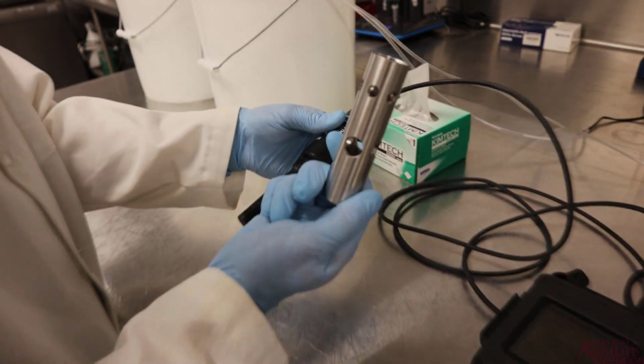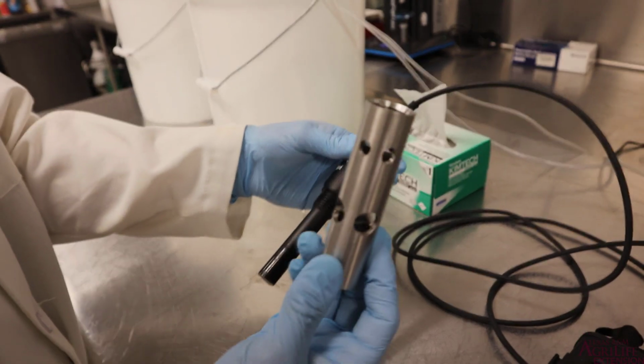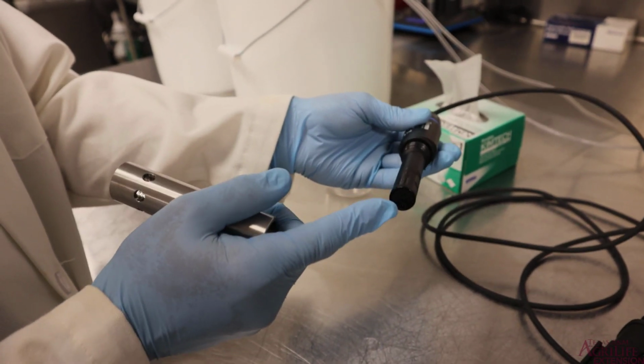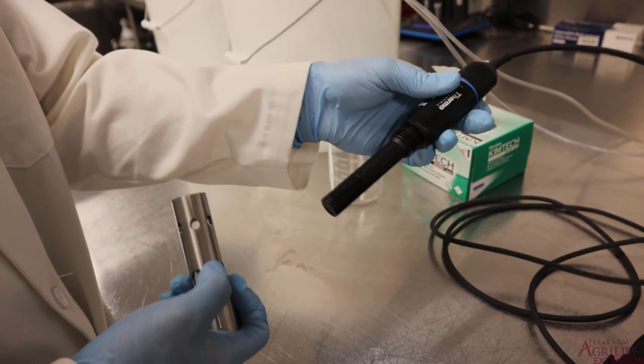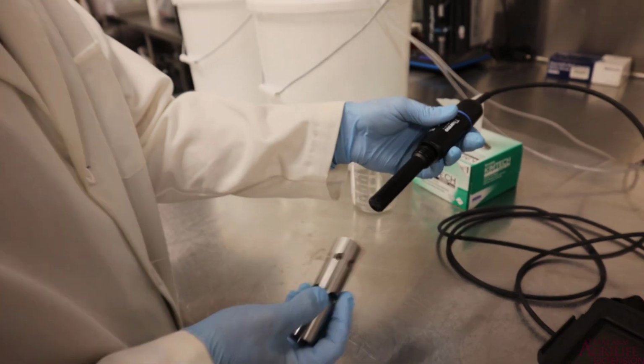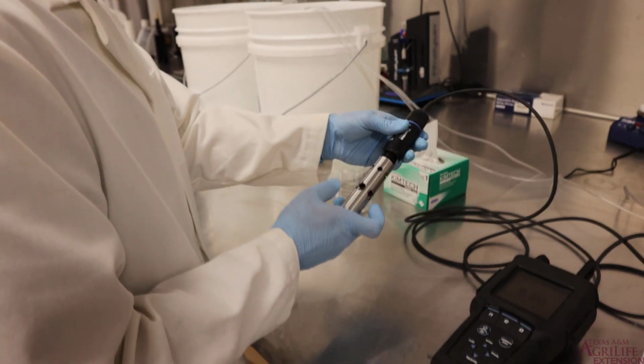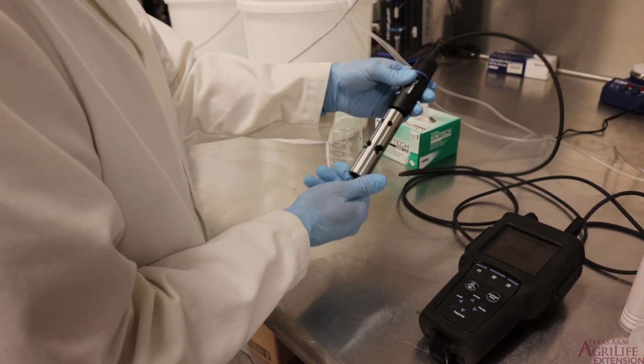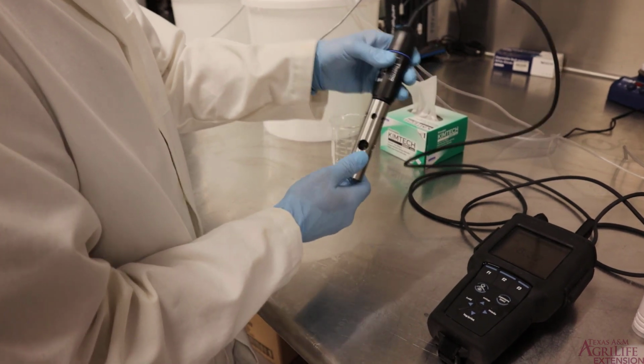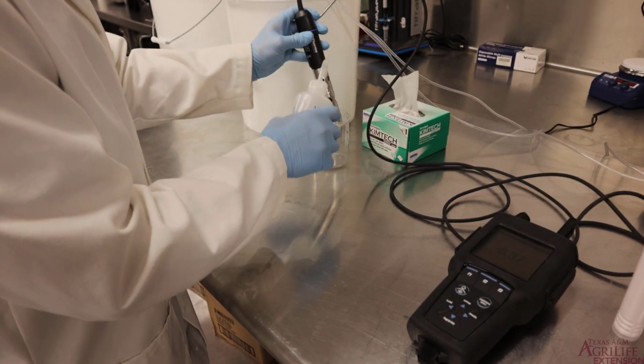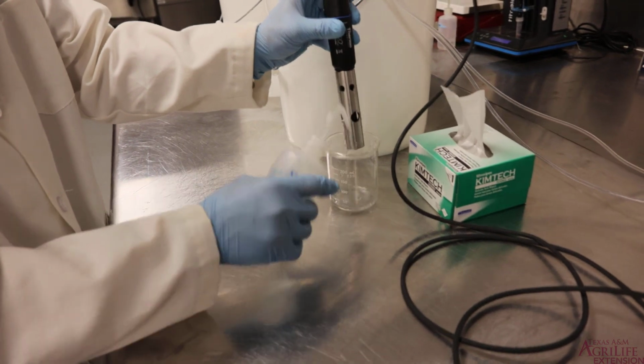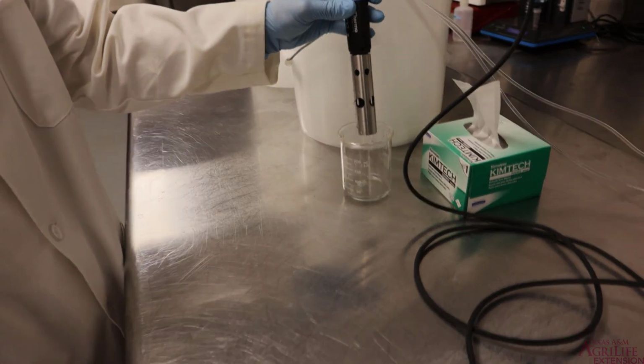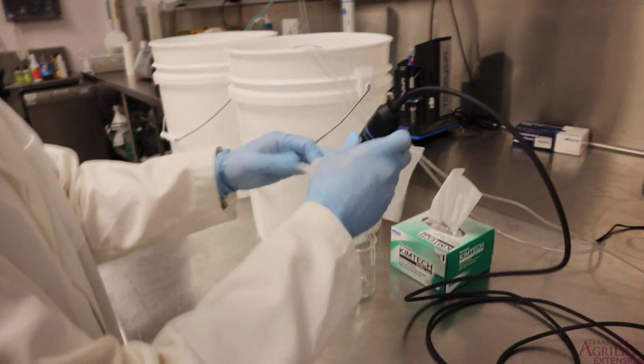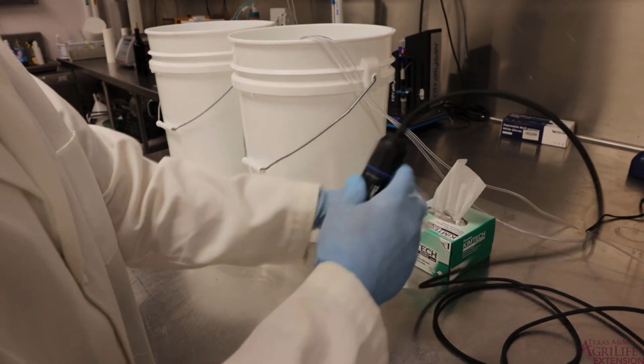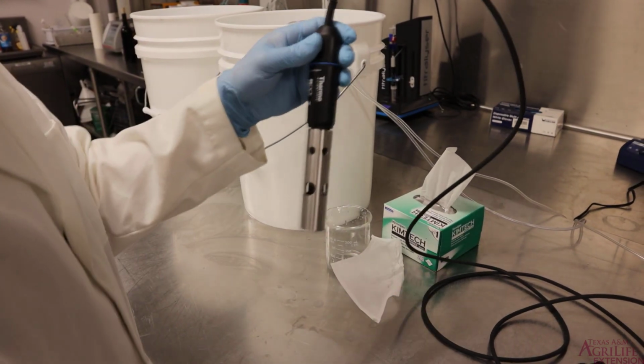We'll use this metal sheath. This piece right here protects our probe, protects our cap, so it doesn't bang around in a stainless steel tank, cause damage to the probe, and affect the life of the probe. So we'll go ahead and just screw that on. We can give the outside casing a rinse. The probe gets rinsed as well while we're doing that, since there are some holes in there. We can give this a wipe, and now we're ready to go out to our tank.